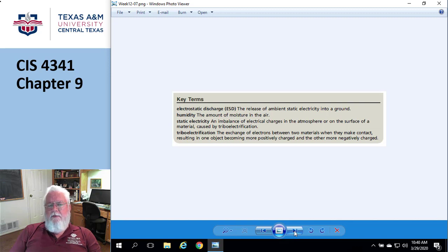Now, you might think, well, wait, do I take humidity out of the air or do I put humidity into the air? Yes, there's a range of humidity, okay? And I'm making some of this up because I really don't know. But somewhere between 25 and 80% is the range they want the humidity in. They don't want too much humidity and certainly not condensing. You know, they don't want water dripping down the walls. And they don't want too little humidity. So the HVAC systems that are designed for computer rooms are designed to keep you within that range between the two numbers, because outside the two numbers, if it's too much, it's going to drip and cause problems. If it's too little, you're going to have electrostatic discharge. Okay.